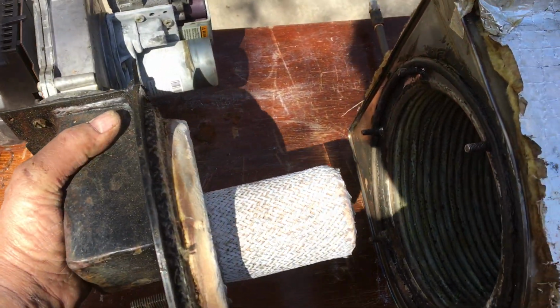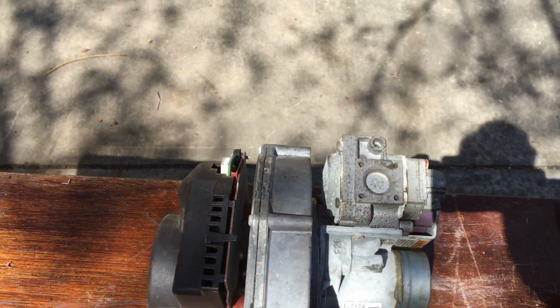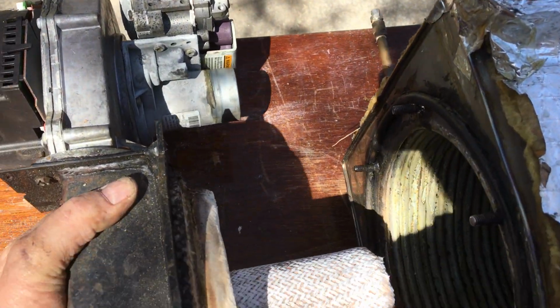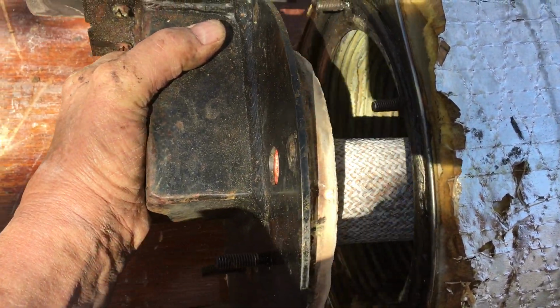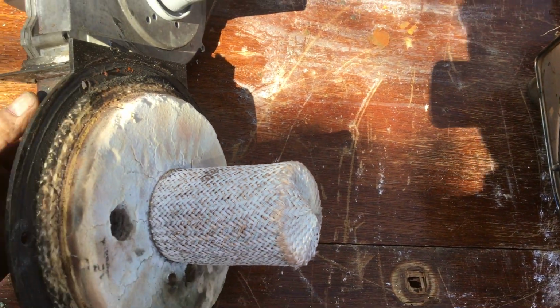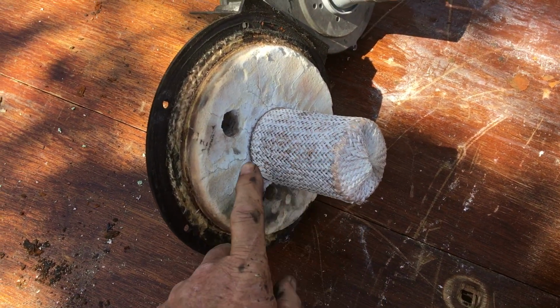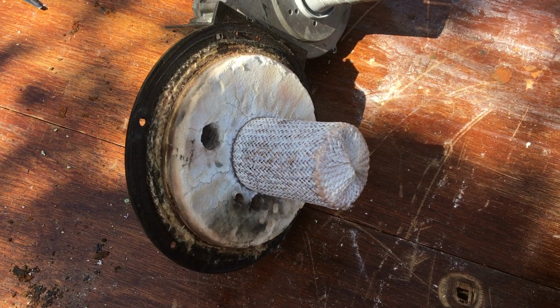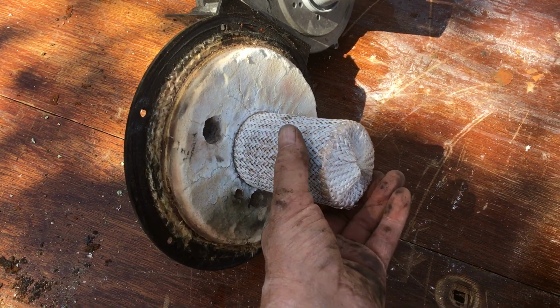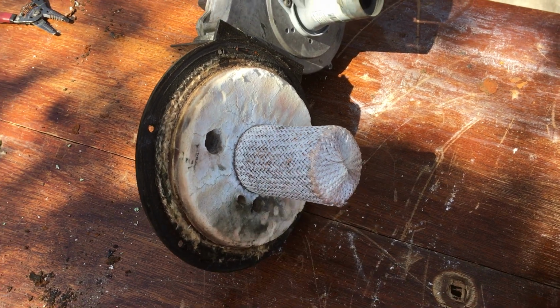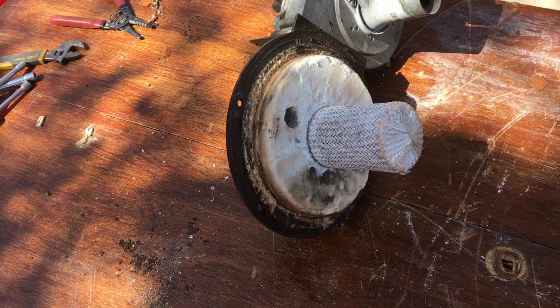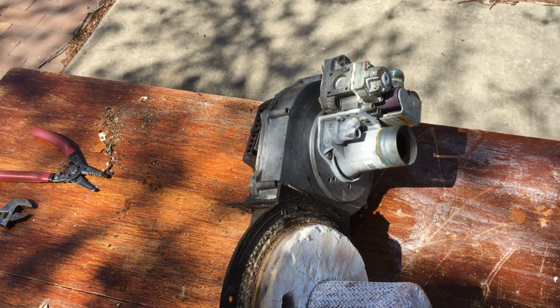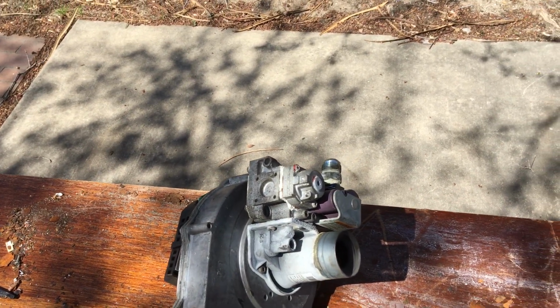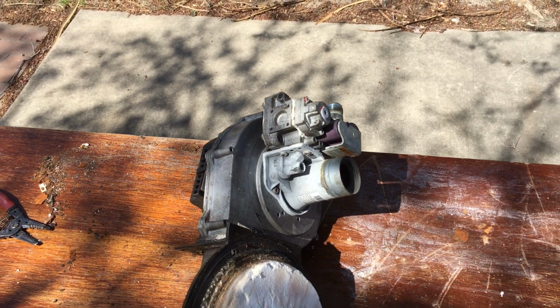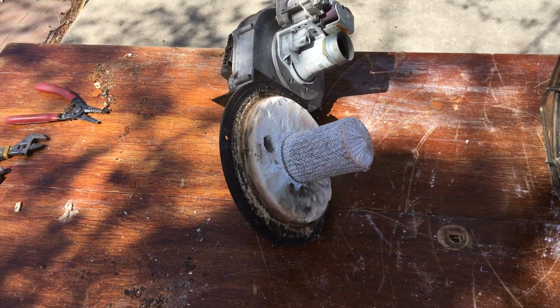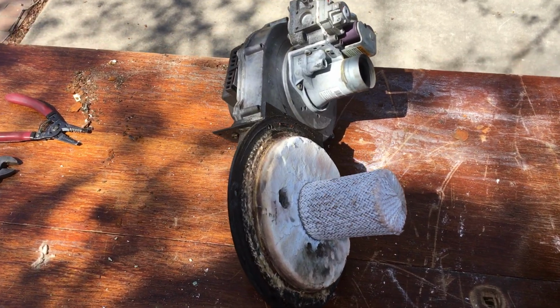This is the burner assembly. It's got the blower, gas valve, all that went into the heat exchanger like this. So there's the burner, refractory material. I'm impressed, it's all intact. This is one of the better ones I've seen in a boiler that's 14 years old or so. So this whole assembly I'm going to save for potential replacement in some other T-Series boiler, at least to get it running for a while.